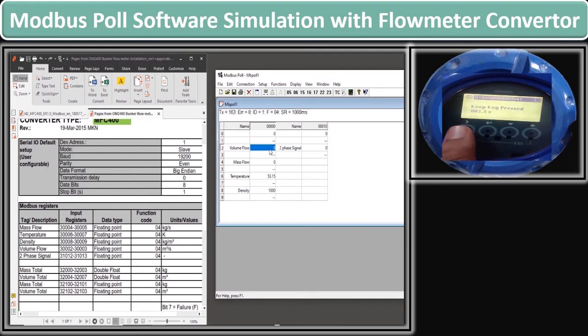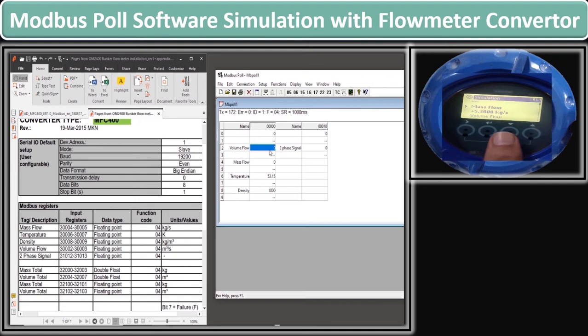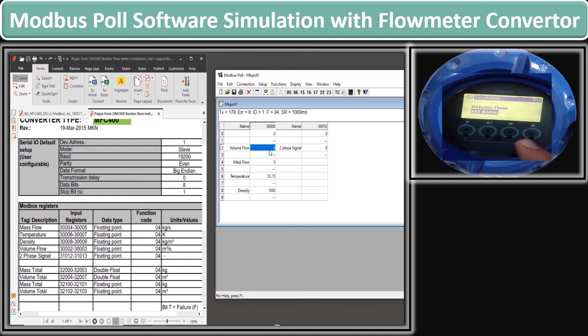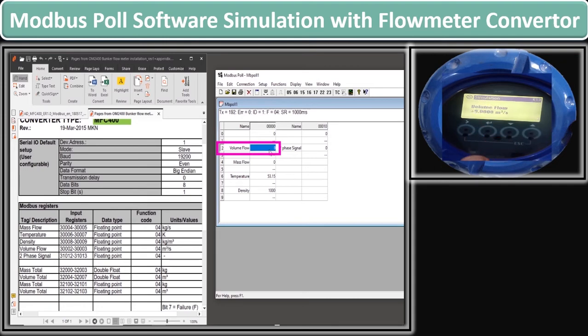First we simulate the value of volume flow on the flow meter. You have to press the Enter key for two seconds, go to Simulation, go to Volume Flow, then enter the set value. Here you can give any value you want to simulate. We set the value to 9 m³/s. As we enter and save the simulation at the transmitter side, we get the value 9 on Volume Flow on the Modbus Poll side as well.